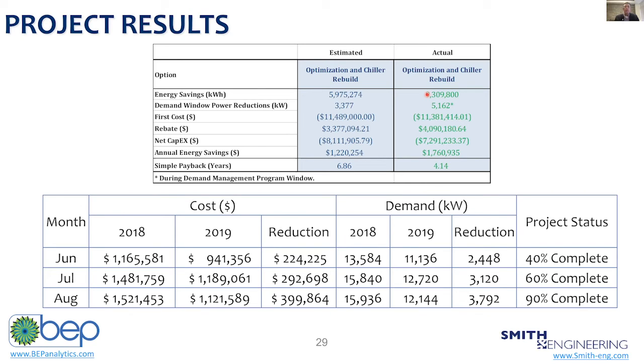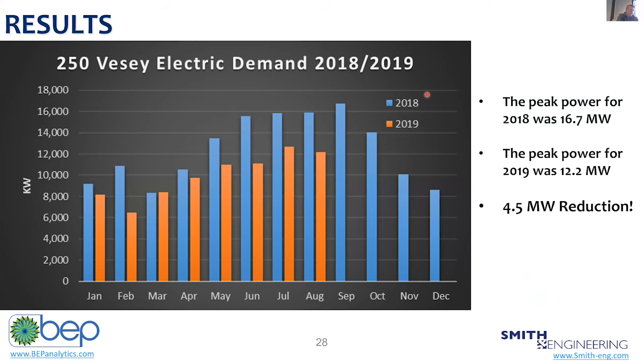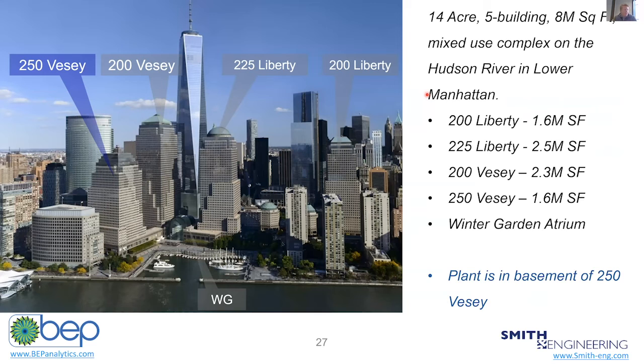Was the 250 Vesey CHW plant that you showed us using the Hudson River for cooling? Oh yeah, sorry, that was using the Hudson River for cooling. I have a tight presentation here, but that plant actually has pump in, pump out sensible thermal storage. A competitor came in and said, hey, we want to put in latent thermal storage or an ice plant. We said, hey, this is the only sensible storage plant in Manhattan, because why is there not sensible storage in Manhattan? We don't have the real estate, right? So the fact that this thing got put in in 1983 is incredible.